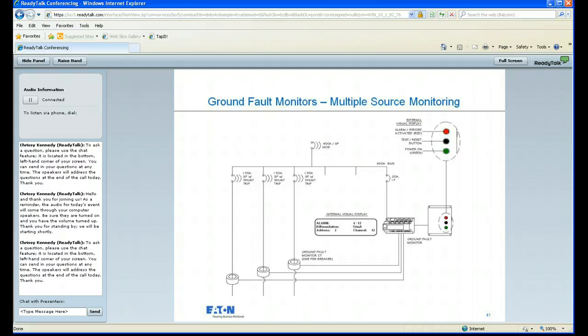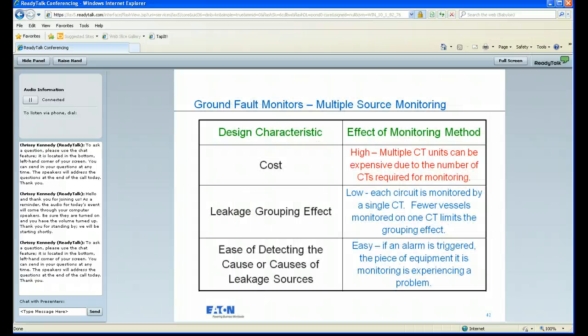Next thing we'll look at is a multiple source monitoring device. With this sort of system, you're going to have a single current transformer, a single CT, provided for each circuit breaker. So this circuit breaker has its own down the line. These devices are also going to send their information back to the monitoring device, and depending on the system you have in place, that monitoring device can send out a small signal turning off your circuit breakers. So whether you want to see a visual alarm or whether you want to have the power for that monitor go ahead and turn off the circuit breaker that's causing the issue, you can set the system up either way.